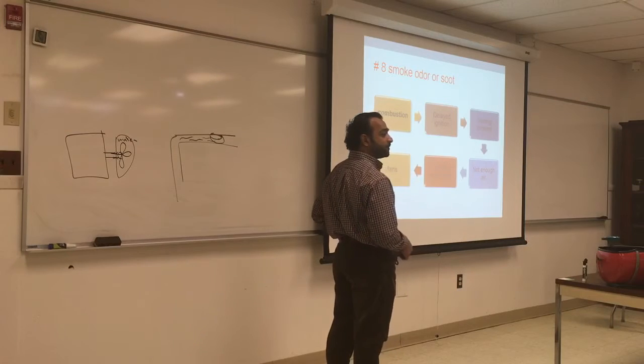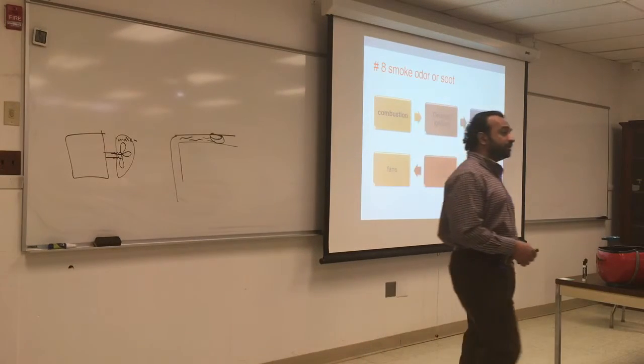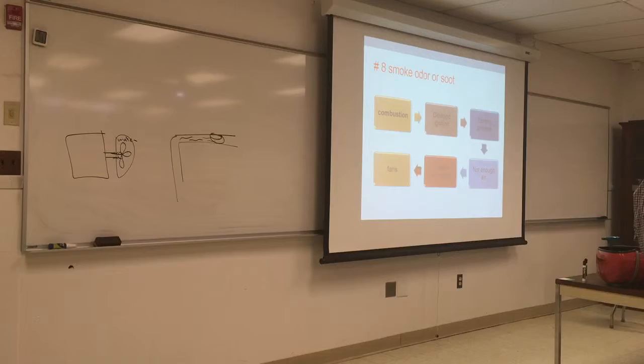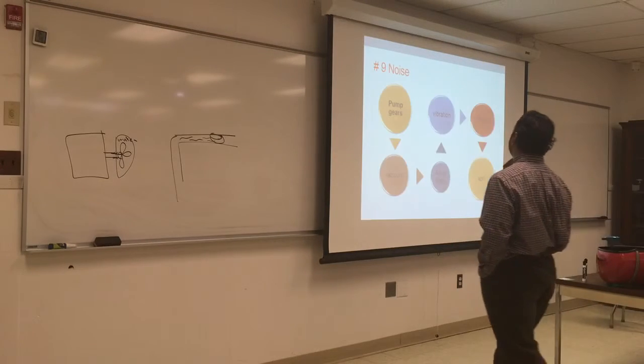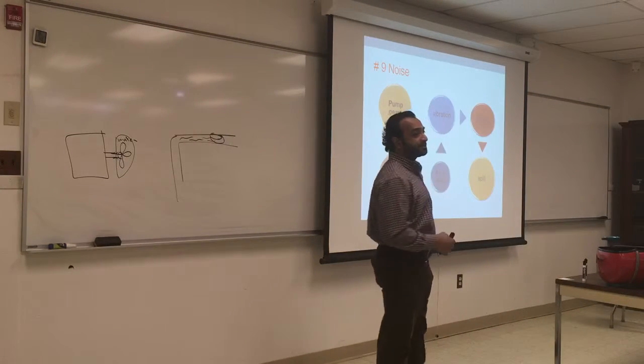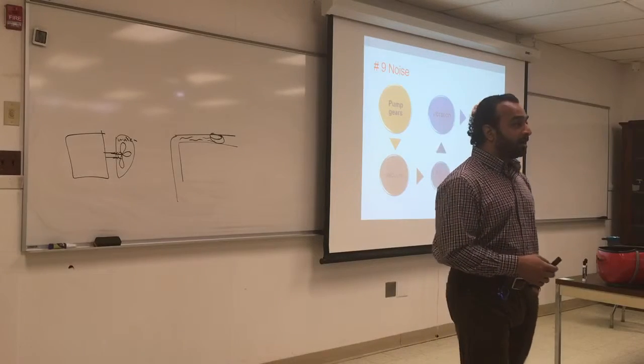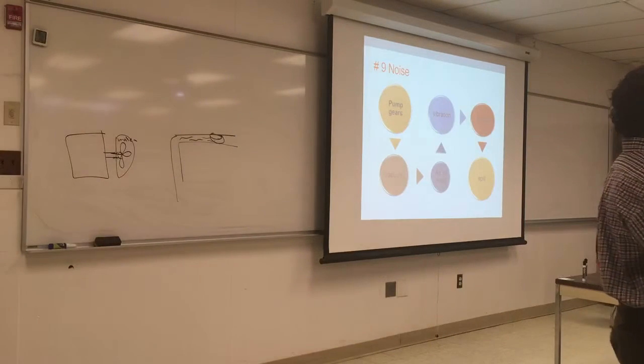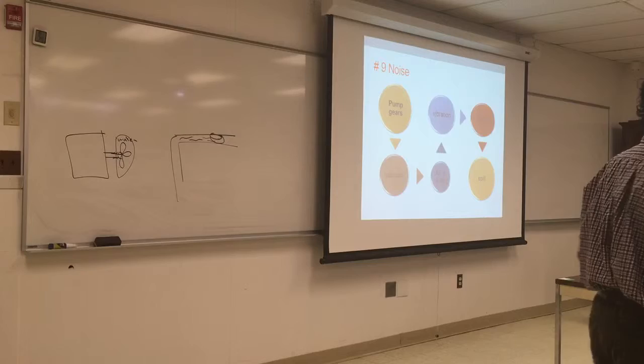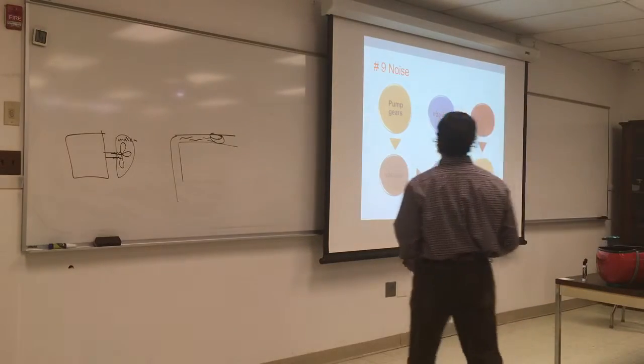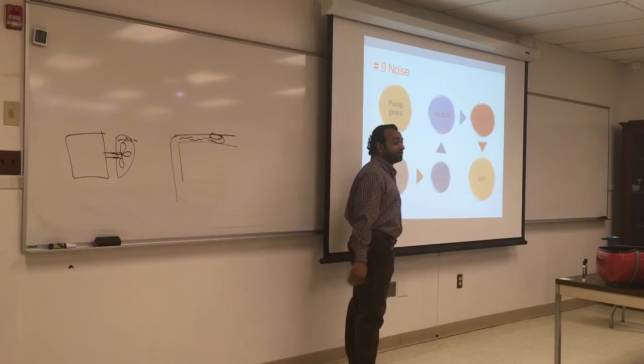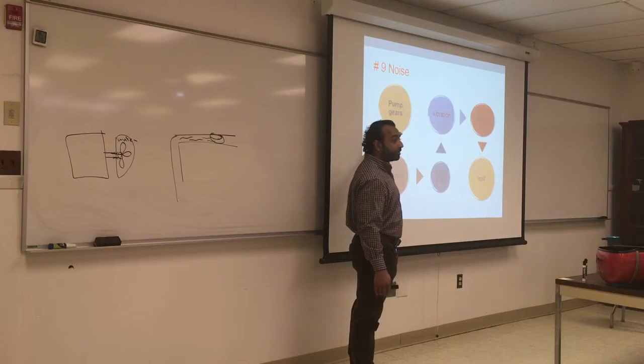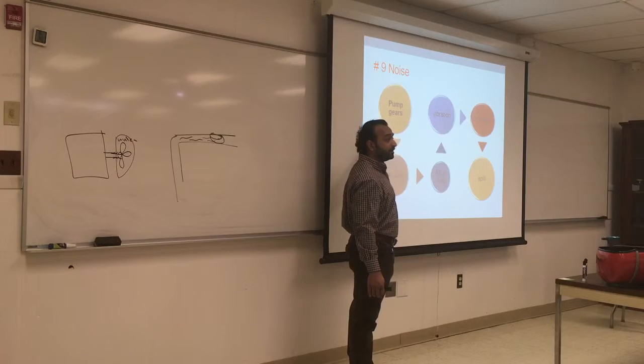Check the fans. Sometimes the fan gets burnt out, or they get something stuck in them, so check the fan is not giving off smoke. If you have noise, again, optimally the system should run smoothly. You should not hear any irregular noise. If you have any noise, it's got to be something that's on the verge of breaking. Pump gears could be broken, impellers could be missing one of the fins.